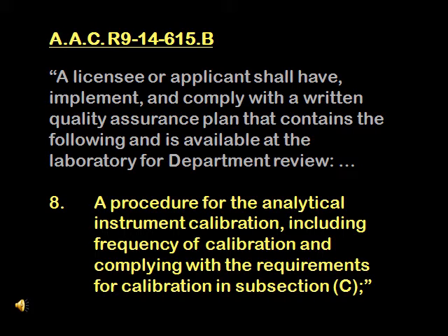Number 8, a procedure for the analytical instrument calibration, including frequency of calibration and complying with the requirements for calibration in subsection C. The specifics for calibration by each method may be contained in the lab's SOP if stated as such in this quality assurance plan.